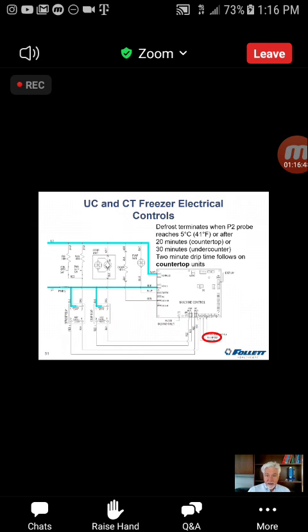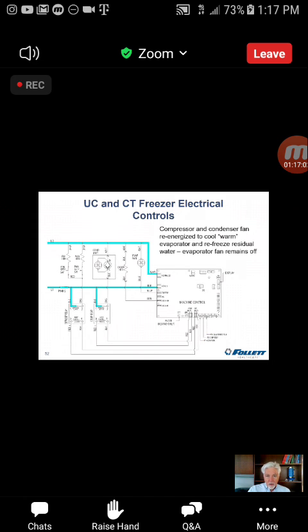Drip time simply means nothing happens. No fans are running, no heaters are on. It just allows additional time for that water to run off of the coil and go down through the evaporator drain pan and drain tube. All right, 2-minute drip time. And then we fire up the unit again. There's no drip time on an under counter unit. But notice, we're only turning on the compressor. We are not energizing the evaporator fan again.